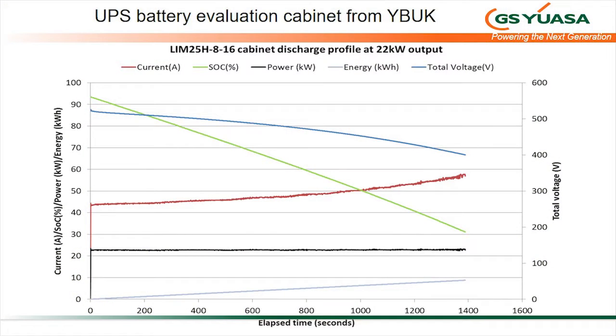This is sharing some results of how the batteries are actually discharging. So this is the time along the bottom. This was 22 kilowatts, a relatively lower rate discharge, and you could take 22 kilowatts for just about 24 minutes. You can see the blue line, so this was a constant power discharge, and the voltage just tapered away quite normally. This could almost be a lead acid battery discharge performance, except that you haven't got the coup de fouet, the dip and then recovery that you often see in the voltage for a lead acid battery.